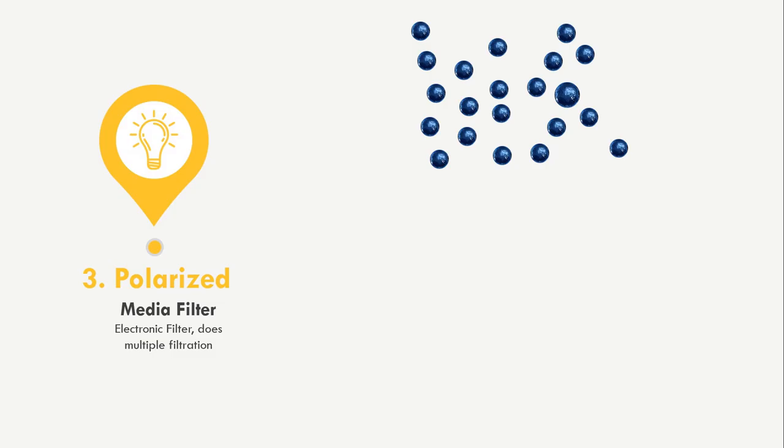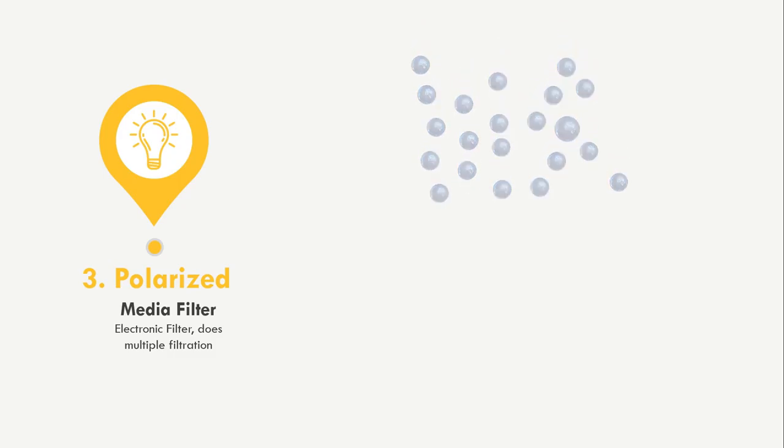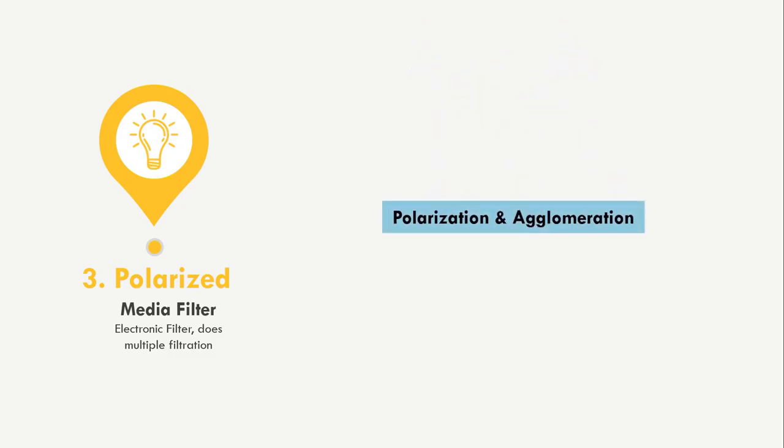The third filter is the Polarized Media Filter. This is different from a negative ion generator and does not cause generation of ozone gas. Filtration through polarized media is a multi-step process: first, impingement (same function as the pre-filter); second, polarization, where airborne particulates get polarized due to high voltage of 6,000V to 75,000V; third, agglomeration, where polarized particulates strike the filter or attach to each other to form larger particles.